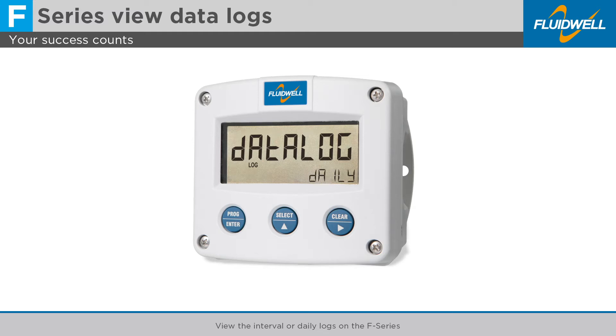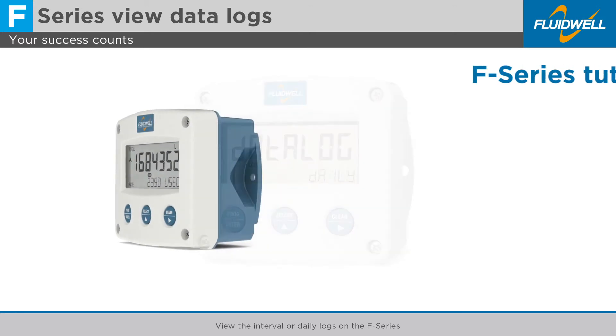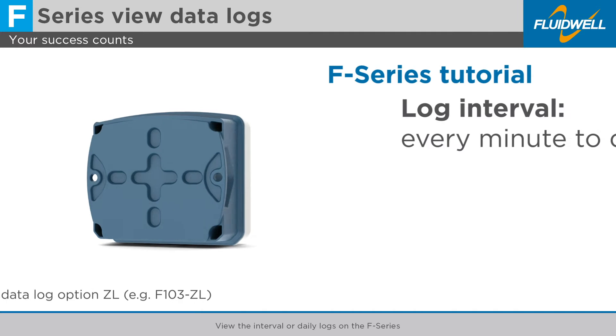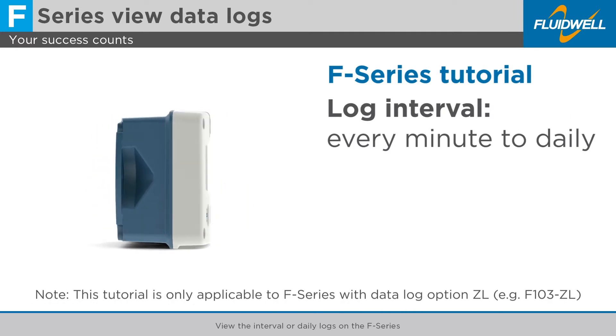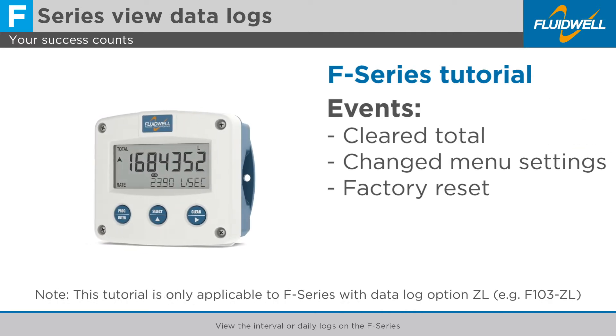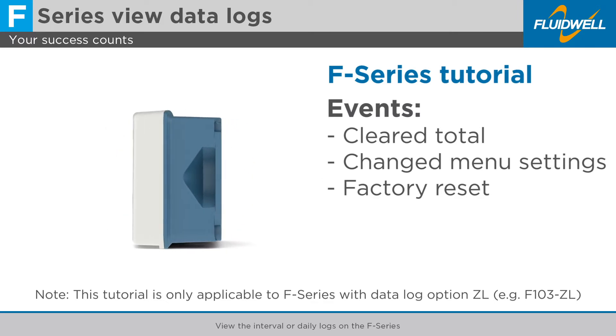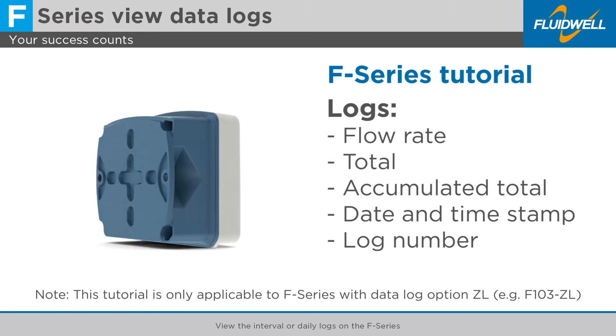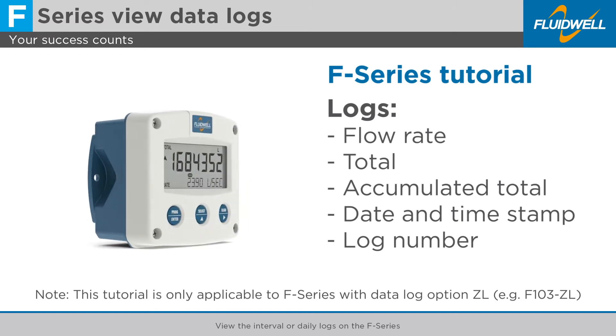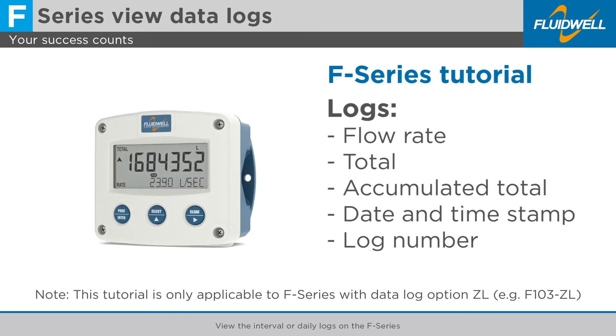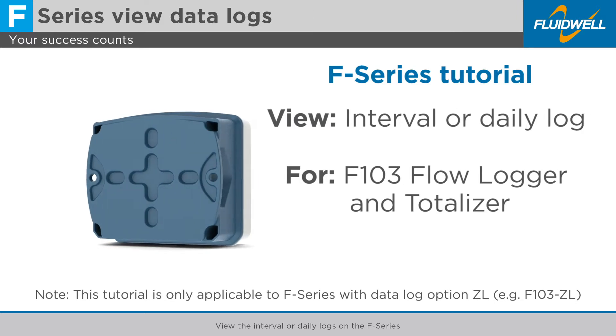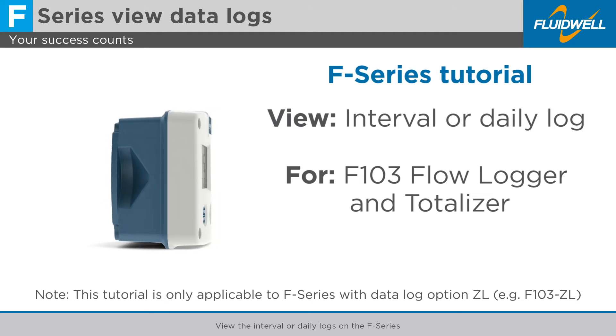When you need to easily monitor your flow measurements and historical data events over time, the logging feature on the F103 is the perfect tool for you. The log interval can be user-defined from every minute to daily. Events such as cleared total, changed menu settings, or factory reset can also be logged. Each log contains flow rate, total, accumulated total, date and timestamp, and log number. In this tutorial, we will show you how to view the interval or daily logs on the F103 flow logger and totalizer.